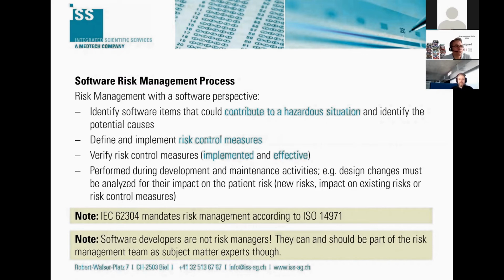And one really, really important part is the software developers are not risk managers. Even if you have a software-only product, risk management is not done by software developers. You need a risk manager for that. The software developers must be part of the risk management team as experts, but they're not the risk managers.